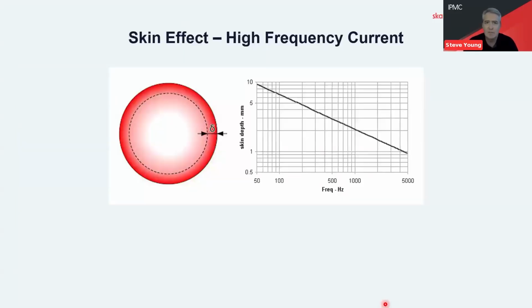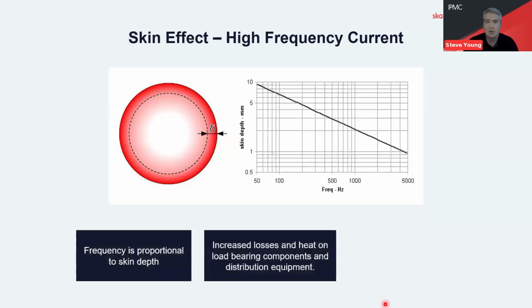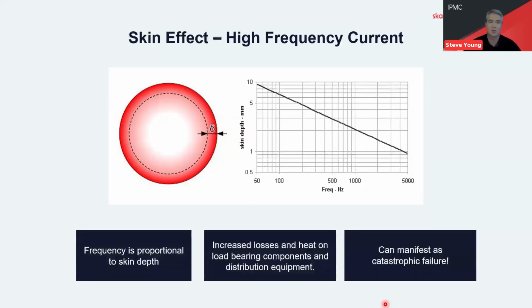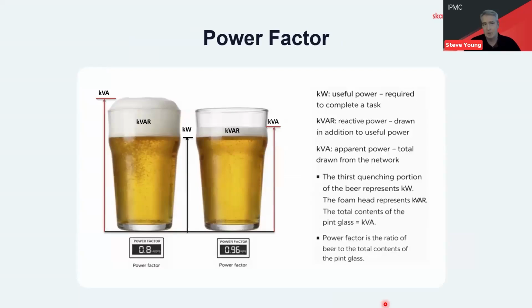So if we look at the impact that the voltage ultimately has on the current, we can look at the skin effect. So frequency is proportional to skin depth. All that means in simple terms is the higher the frequency, the less depth that component can flow within the conductor. So that's going to lead to overheating. It can lead to further breakdown of the insulation, again leading to further dissolved gases within the tank. And ultimately, as we're breaking down insulation, no surprise, this can sometimes manifest as catastrophic failure.